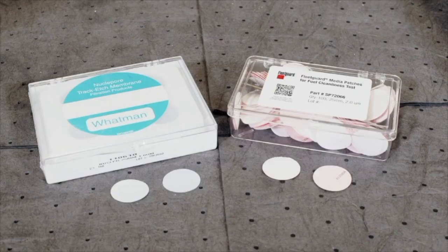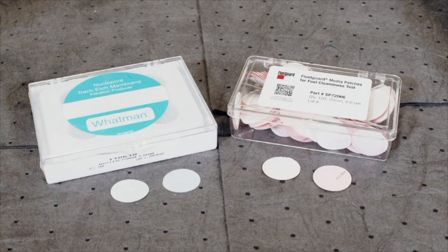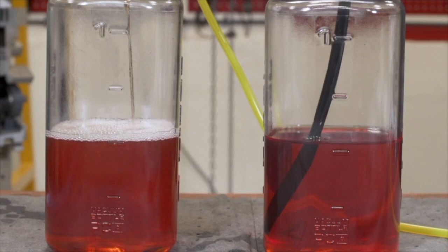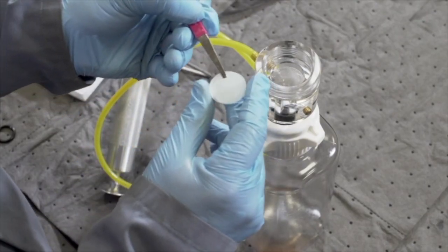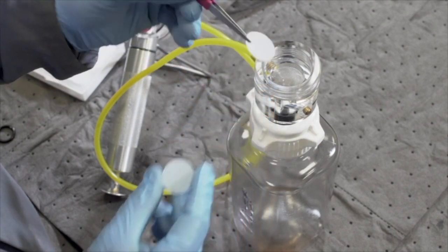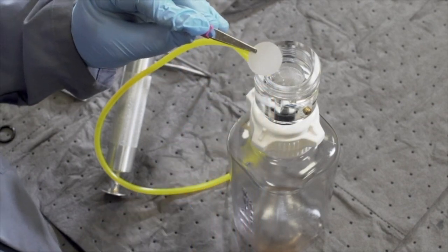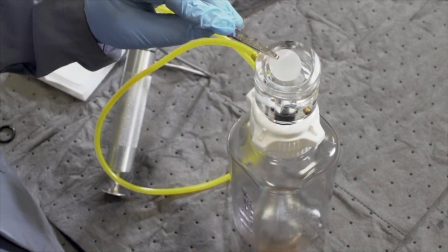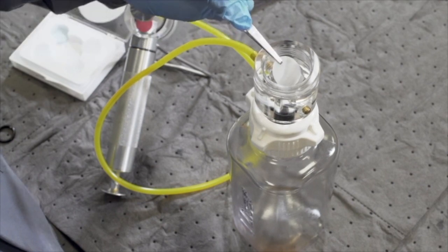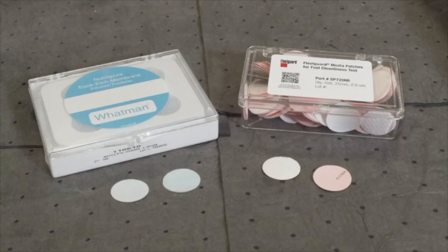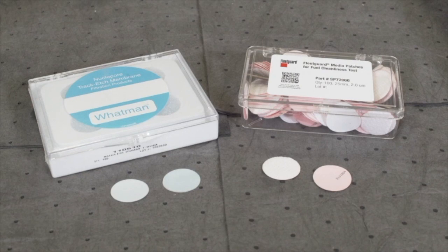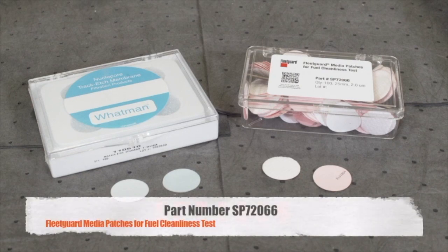Two grades of filter media patches are supplied with the kit: a two micron nanonet media and a one micron pore membrane. Most fuel can be effectively tested using the two micron nanonet media. The one micron membrane is more sensitive and suitable for special cases where there is a need for lab analysis of the contamination found in the fuel. Additional patches are available and can be ordered using part number SP72066.